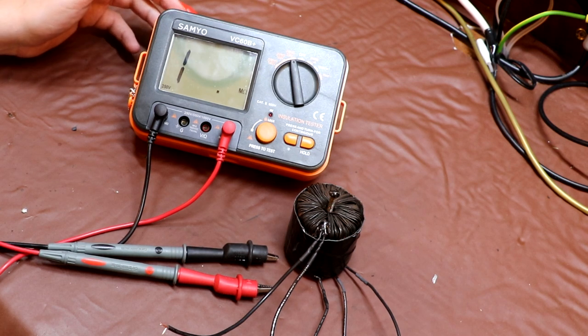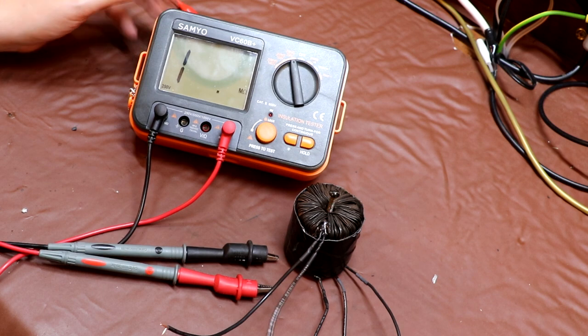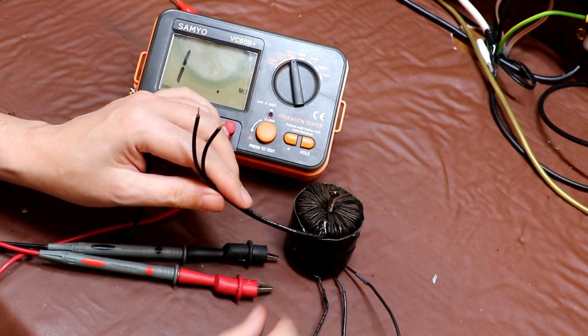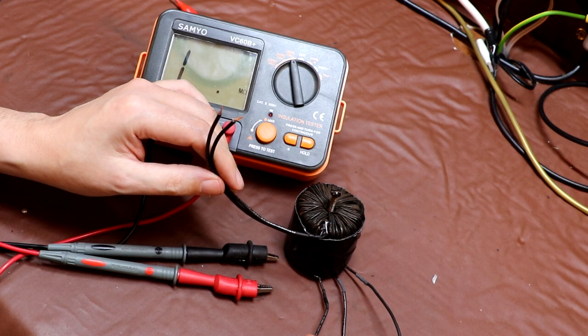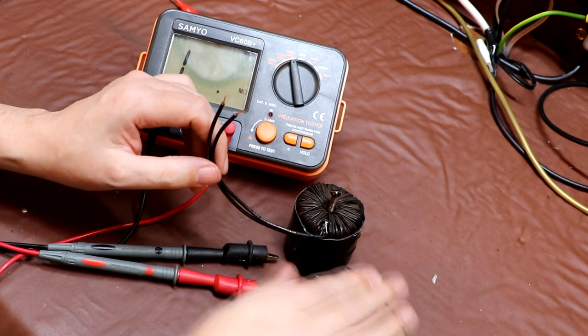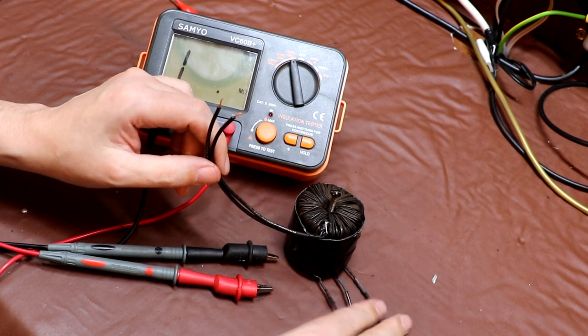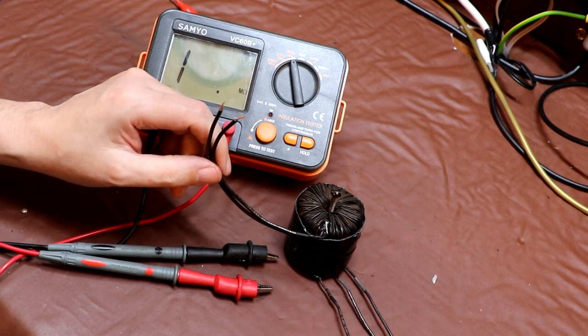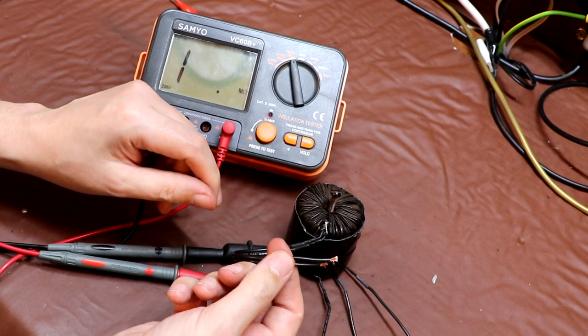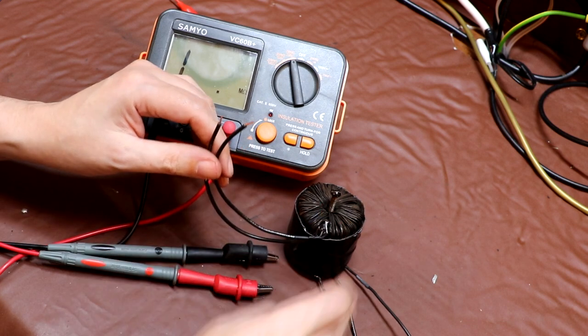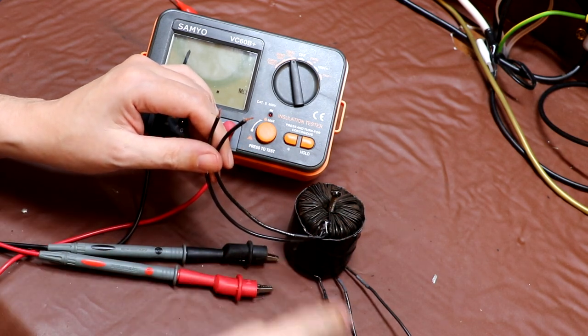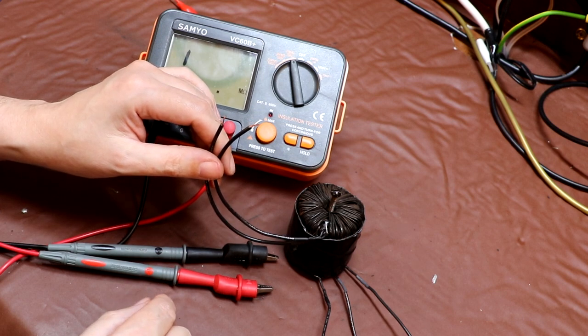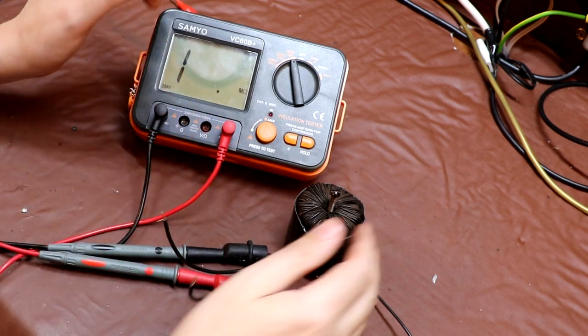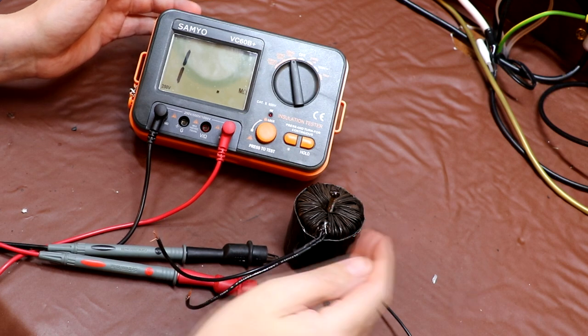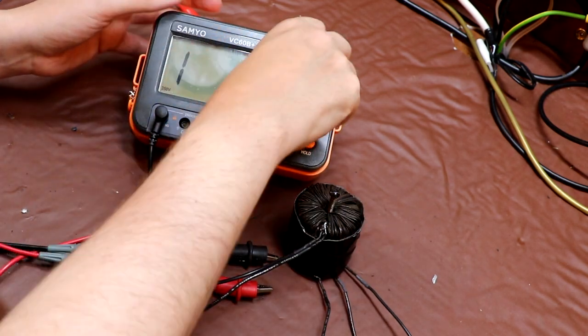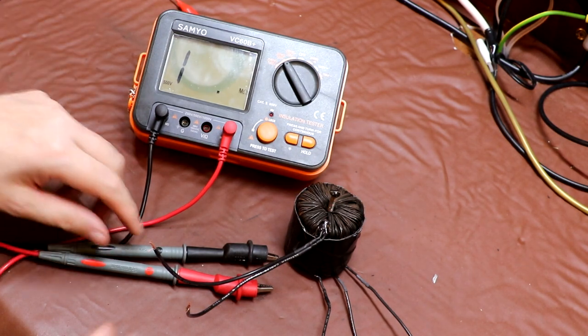So again, typical transformer tests that you do on any transformer, you want to do an insulation resistance test between the primary and the secondary windings. In fact, I've got that the wrong way around. The primary windings are at the bottom here with this multi-tapped primary winding, and then we've got the 2 wires here that are the secondary. So you want to look for insulation resistance between the primary and secondary, and you're looking for a value as high as possible. Now typically you test at twice the rated voltage, so on this meter that'll be 500 volts.